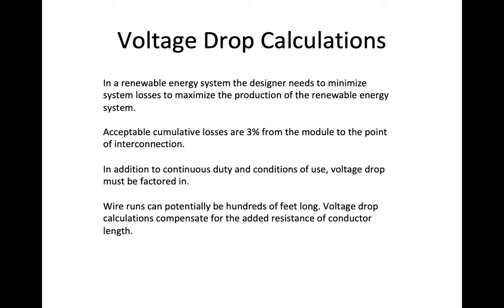Now, in the renewable energy world, we want to limit our voltage drop to 3% to 5% based upon the fact that we want to get as many electrons off our array or off our wind machine to the utility. So we don't want to waste any. And so if we have great distances to cover, hundreds of feet or thousands of feet, we have to upsize the conductor in order to manage the losses in our conductor run.